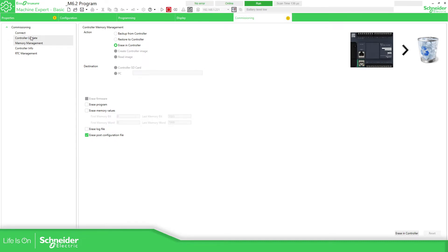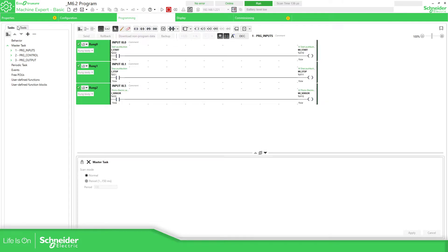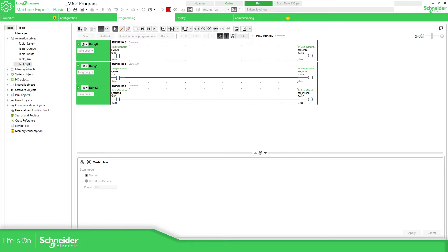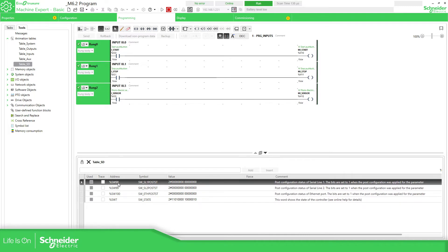If you want to check whether the controller has some post configuration files, you can use this. If nothing is checked, it means there is no post configuration. There are also some internal system word variables — SW98, SW99, and SW100 — that allow you to see if there is a post configuration already set for serial line 1, serial line 2, the Ethernet port, or the controller. This is one way to do it in the software and an easy way to see if you have something already in there.